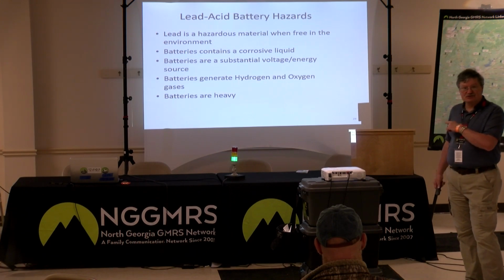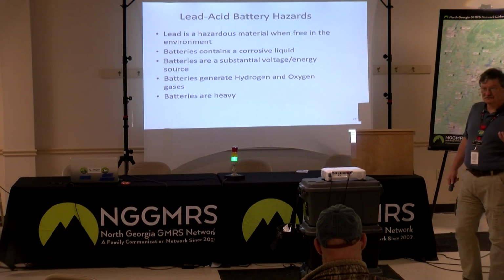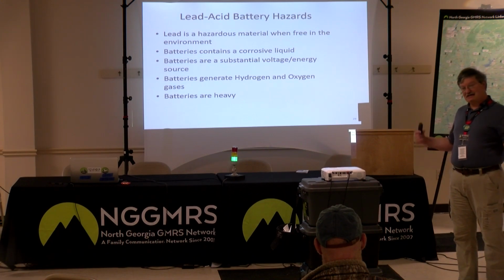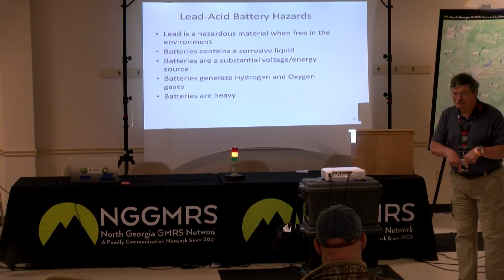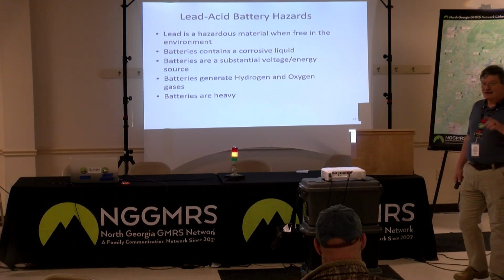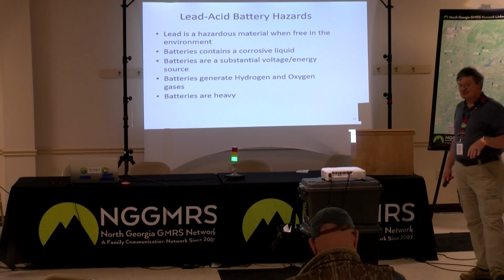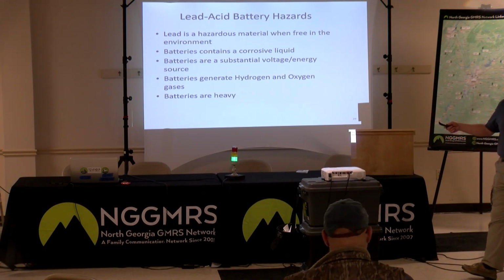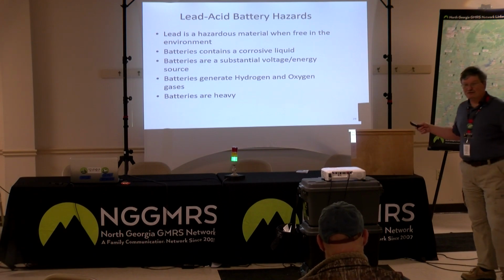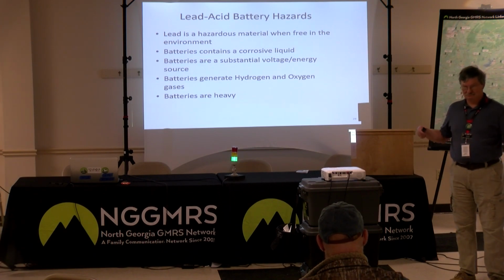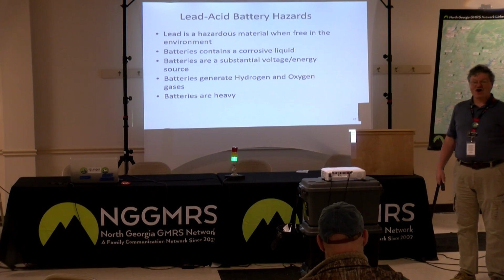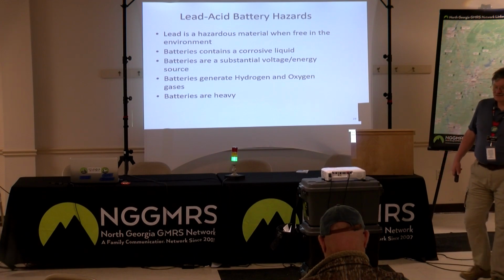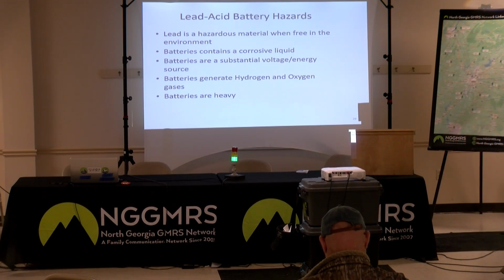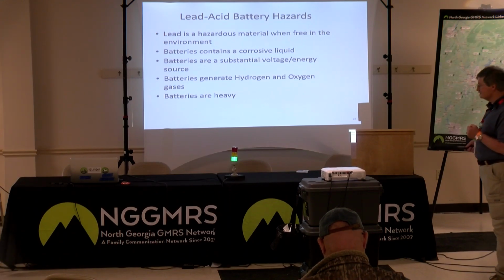These standby batteries we showed earlier, a number of them have a flame arrestor, so if something happens outside, it doesn't get inside and make the cell blow up. A lot of places require ventilation of big battery rooms. I've been in a battery room that makes this room look small, with hundreds of battery cells for a big installation, with special ventilation to make sure they don't build up an explosive concentration of gases.